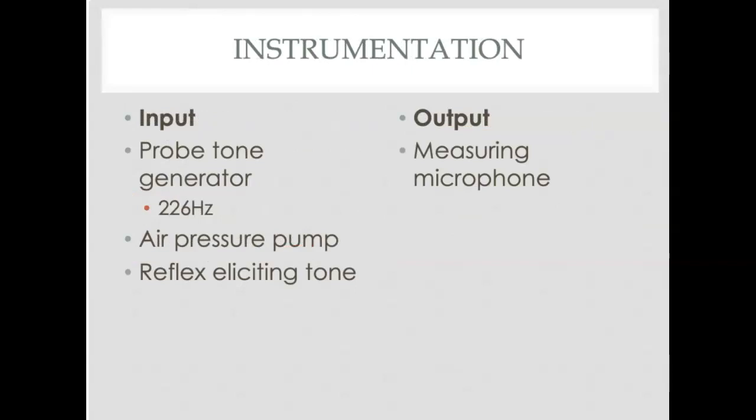The input to the system is a probe tone generator. We use a 226 Hertz tone because for adults, that's the tone that has been found to work the best. We use an air pressure pump, and then there's also an acoustic reflex eliciting tone generator. The output essentially is what we get in the microphone.